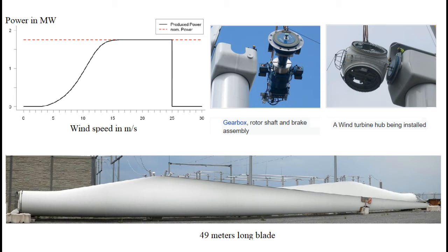But if wind speed changes to cross the limit, then pitch angle is another control that the control system performs using sensors. When wind speed increases, power extractable increases by the cube of wind speed, but rotor speed is kept within limit to keep the blade in a safe stress limit. This suggests that torque transferred with rising wind speed is increasing by the cube of wind speed. This increasing or decreasing torque must manifest in a change in current supplied to the grid since RMS grid and alternator voltage is constant.